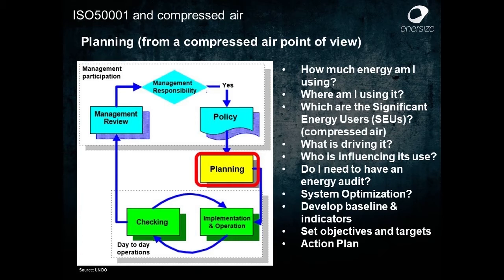So also, what is driving it? Of course, production will probably drive a compressed air system up and down depending on how much you produce, but also weather, if you are dealing with centrifugal compressors, will influence the energy consumption. And who is influencing its use could very well be staff: the operators of the machines, the end users, the operators of the compressors. And do we need to have an energy audit? I would say yes. Maybe they know very well already what they are doing and where they are consuming the energy. System optimization: you should ask yourself, will it make sense to look at the end use when it comes to compressed air? And for sure, yes.